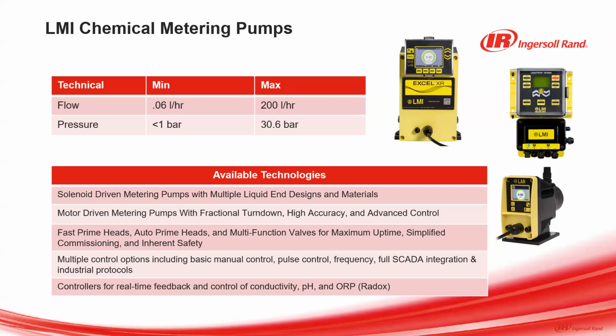There's multiple control options for these pumps as well, including simple on-off control to the pumps. There's pulse control and frequency, which can be brought from a controller or a SCADA system. And there's full SCADA integration with 4 to 20 milliamp signals and dry contact relays, as well as the available industrial protocols, including Modbus over RTU, TCP, Profibus, and Profinet in select models. The controllers of LMI pumps provide real-time feedback for control of conductivity, ORP or redox, as well as pH control.